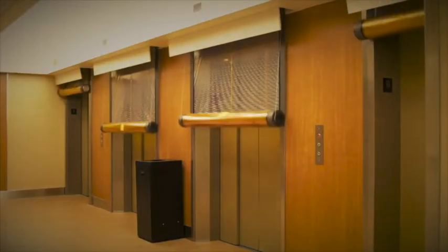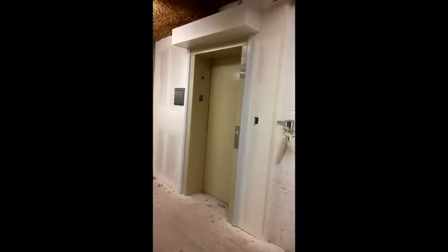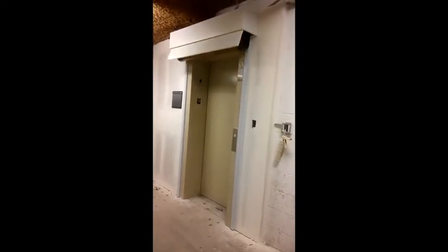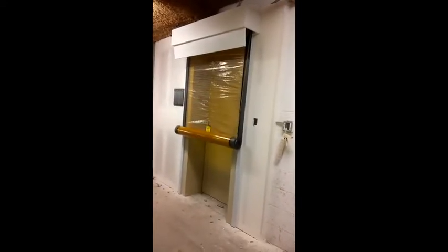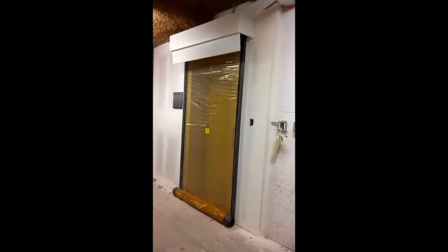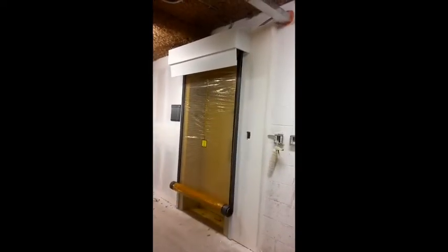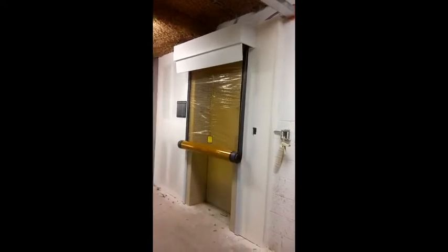In its simplest form, a fire curtain is similar to a fire door, but it's much lighter, and the fire-rated material is hidden in a manner which automatically unrolls downwards when needed. Fire curtains are automated, and they drop down upon activation of the fire alarm panel or individual smoke or heat detector. Once they have fallen, they secure the opening and will withstand a fire for between 1 to 4 hours, depending on its fire rating. The curtains also seal off the hoistways and stop the chimney effect and prevent smoke from traveling to other floors. When not required, fire curtains can either be manually reset or automatically retract into their concealed position until they're activated again.